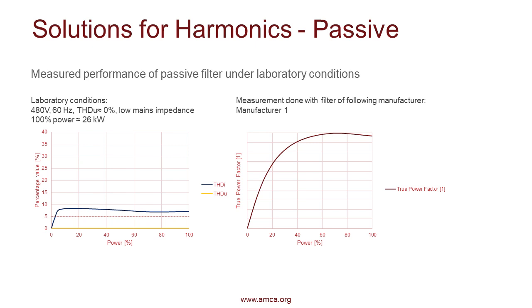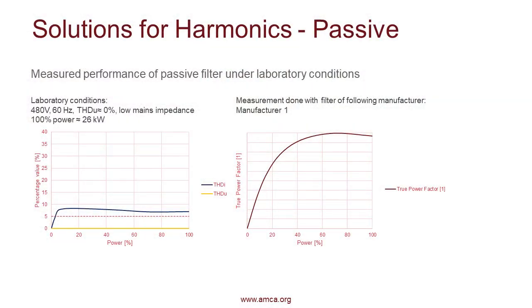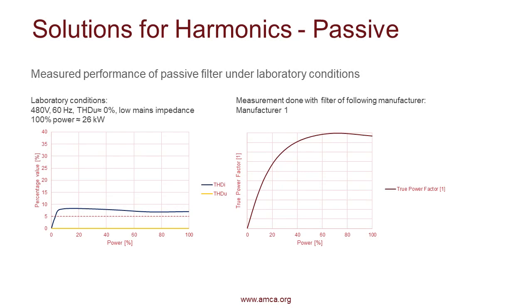So we did some laboratory condition testing. So some examples, we have manufacturer one of a passive filter utilized with a 6-fan array. On the left, we're looking at our total power percentage versus our percentage value of THDI and THDV. We can see our THDV is 0, but we have THDI less than 10%. So this is pretty good. You can see that it's starting to increase a little bit in THDI as you go into a lower partial load. But what's really important is on the right, we're looking at our true power factor. This is the efficiency of your system, efficiency of your fans. And you can see that at 100% load, you're not quite hitting that 1. So you have more foam in your cup, right? Which is not ideal. And then as you decrease further partial loads, you start to see a dip. So this is not really helping with your power factor. It's just reducing that THDI. It's not really increasing any efficiency within your system.